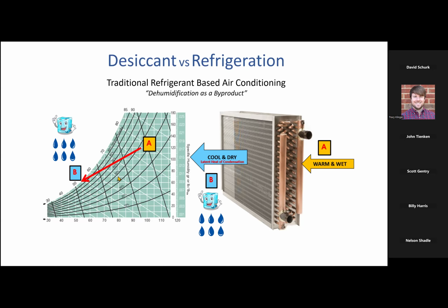Now, that's great if I want to maintain a space somewhere between 50 and 60% relative humidity. By the time it comes back here and absorbs moisture and temperature, probably going to float somewhere between 50 and 60% relative humidity in the space. But what if I need to be down around 30% or 40% relative humidity? Then what I have to do is I have to continue to cool that air further sensibly so that I can remove more moisture over here on the right-hand side, more grains per pound. So maybe I need air coming out at, say, 45 degrees Fahrenheit, 45 degree wet bulb, 45 degree dew point, so I can hit that 30 to 40% relative humidity in the space. Or let's say that's not enough. Let's say I need to be down around 10 or 20 or 25 or 30% relative humidity. I have to then continue to chill this air further and further and further.